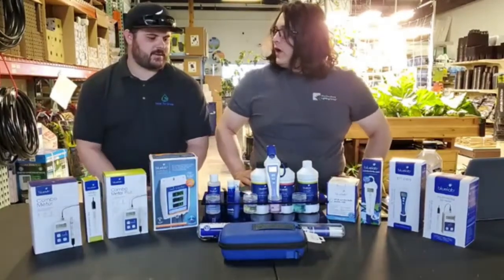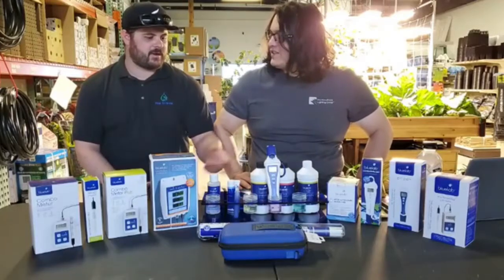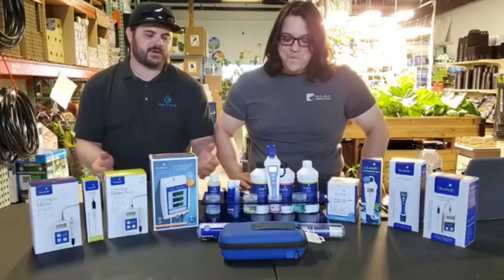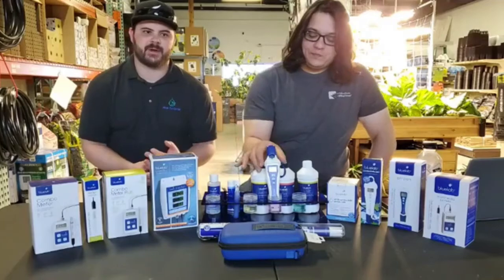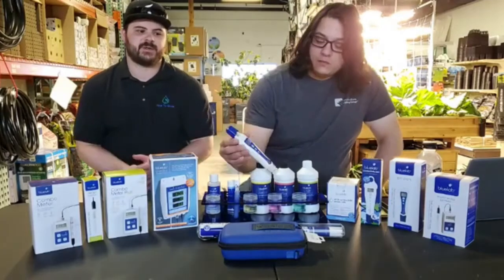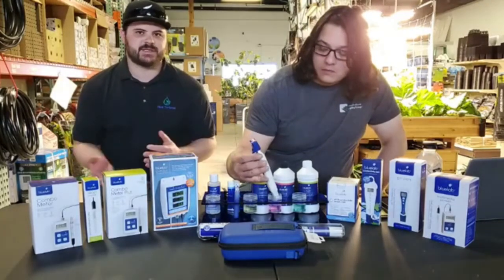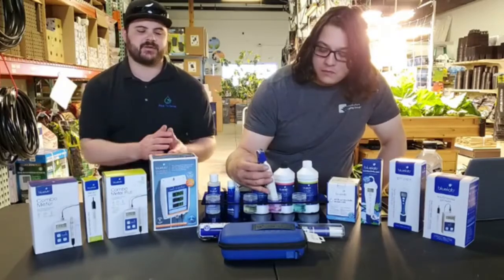So now we're halfway done already. Well, that's pretty much it. When you're calibrating a pH pen, you always want to calibrate multiple ranges in the pH scale, and this just guarantees that your pen is calibrated throughout the full range.